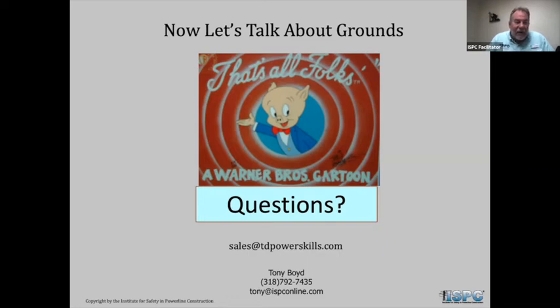So next we talk about grounds, and what I get into is more of the intricacies of bonding the communication messenger wires underground especially, but overhead as well. Your communication messenger wire that is not bonded to the system neutral could possibly, all right, it's not a very high risk, but it could possibly actually acquire some induced voltage from the lines that are on top. And let me give a little bit of an example of that.